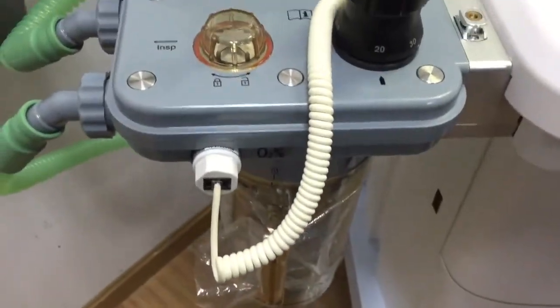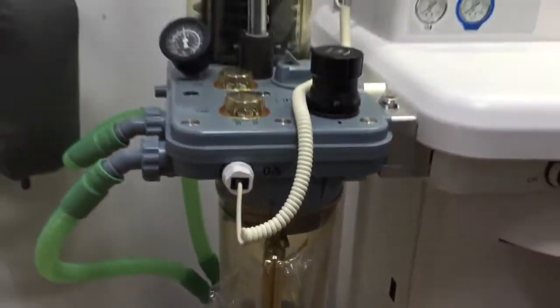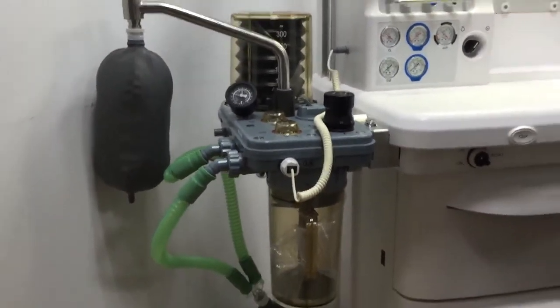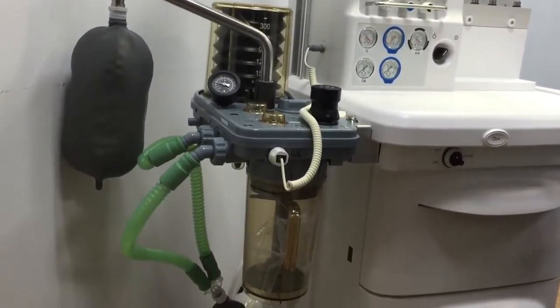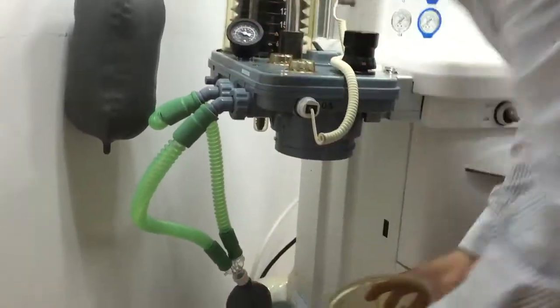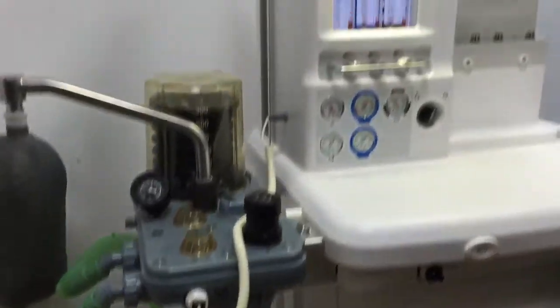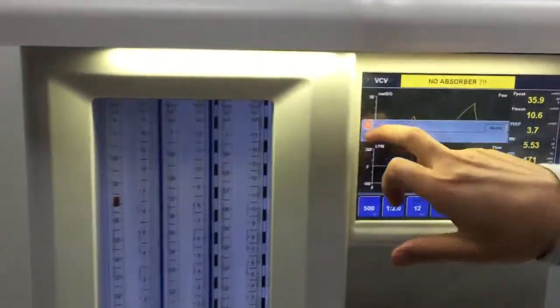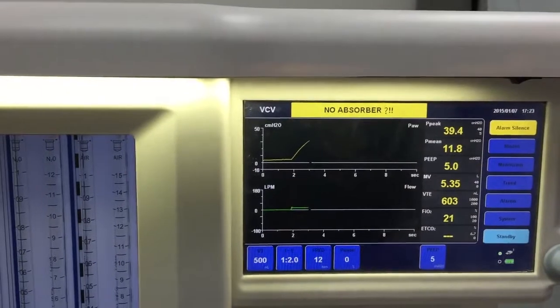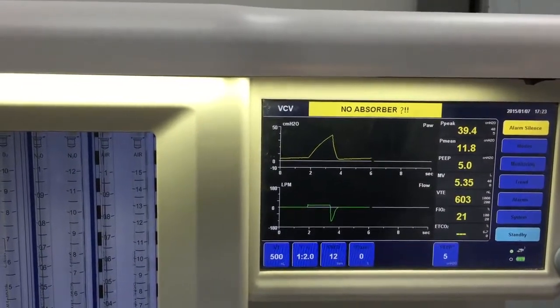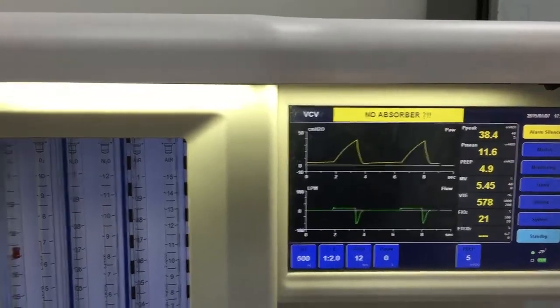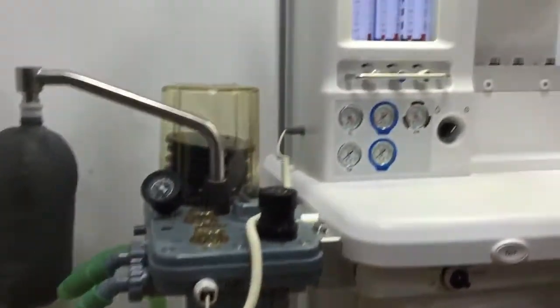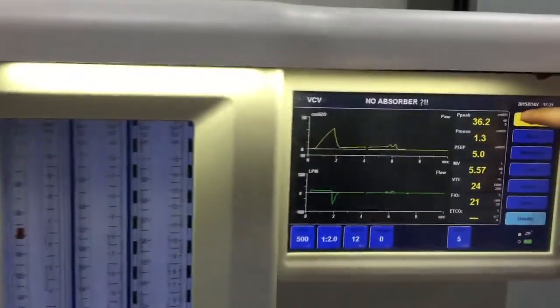And the benefit of our machine is that all the anesthesia machines at Siriusmed have a bypass design, which means you can simply take out the absorber and no leak happens. Then you get a caution, no absorber, which is less serious, maybe just a warning. And we can put it back after we fix the absorber, and then the absorber comes back and we can reset it.